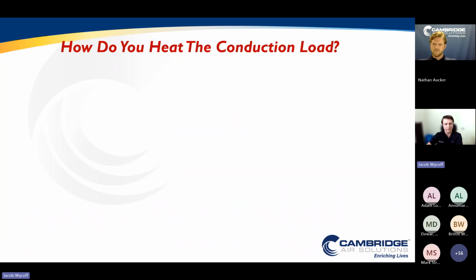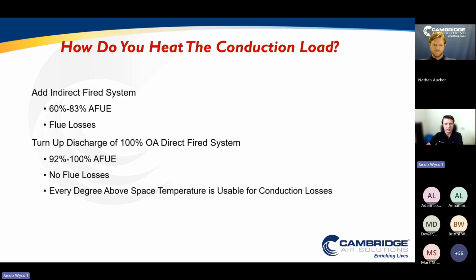And what's the best way to heat the conduction load? So you can add an indirect fired system at the efficiencies we talked about previously. You're going to have the flue losses, but the benefit theoretically is that you can recirculate the air that's already in the space through that indirect fired system without having to heat any more outside air. Another option is to simply turn up the discharge of that 100% outside air direct fired system that you already had to heat the air load. You get the direct fired efficiency, you lose all those flue losses, and every degree you raise your discharge temperature above the space temperature, you're going to get heat that's usable to cover the conduction losses of the space. We call those usable BTUs or net BTUs.